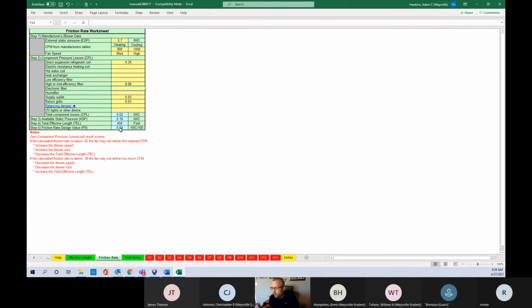So the 0.1 is what we were kind of saying it was going to be. And then in this case, we're going to say it's 0.04. So let me just look at one example of that and see how that changes things. Pull out your duct slide, and let's say we're going to move 1,000 CFM at 0.1.